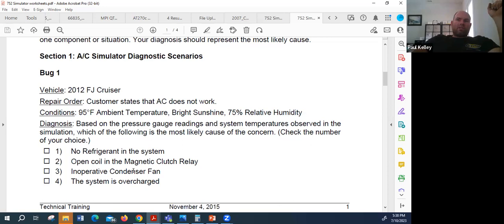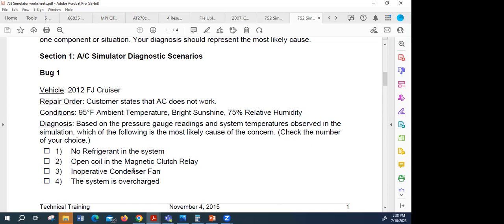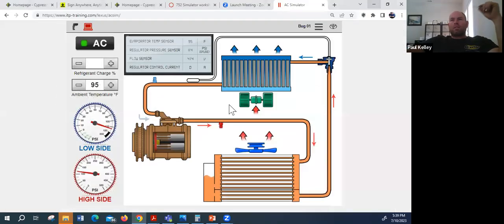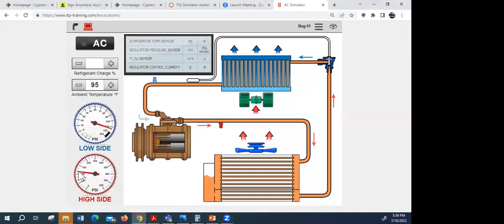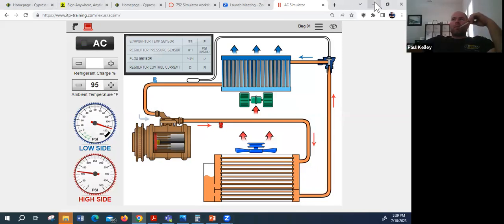Does everybody follow that logic? If your condenser fan is out, that means your condenser is gonna be very hot, and that's the high side. If your high side is hot, what's your pressure gonna be? High, very high. Is that what we had on the simulator? No, we had static.